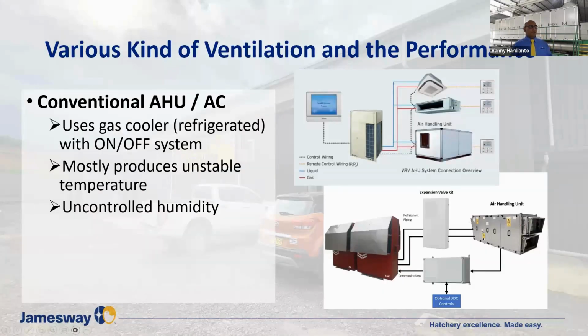In the following time period, refrigerated air handling units, or air conditioning units, started to be widely used. This system can meet the temperature and humidity requirements for the incubators. But because this ventilation uses an on and off cooling system, it results in unstable temperature and humidity in the incubator room.